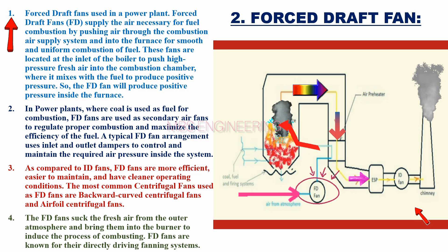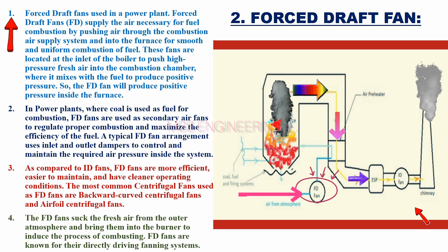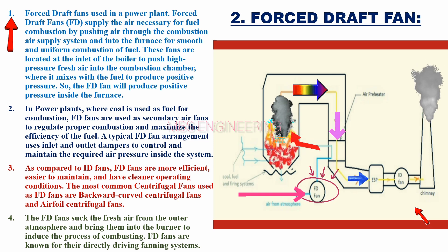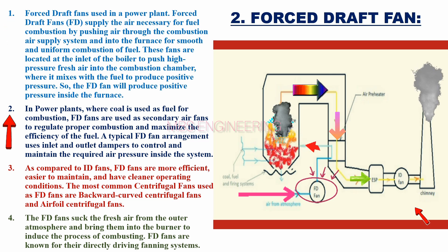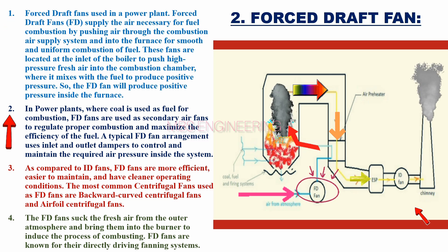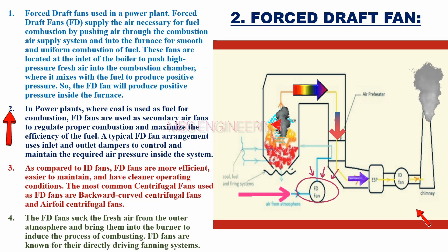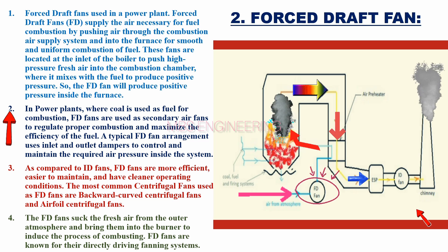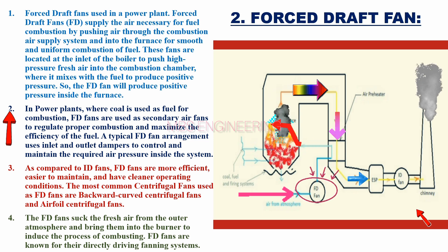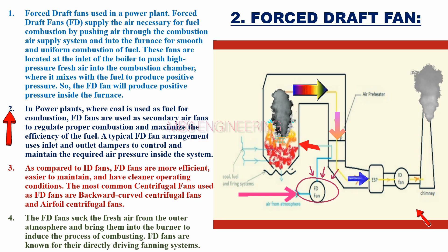Forced Draft Fans supply the air necessary for fuel combustion by pushing air through the combustion air supply system and into the furnace for smooth and uniform combustion of fuel. In power plants where coal is used as fuel for combustion, FD fans are used as secondary air fans to regulate proper combustion and maximize the efficiency of the fuel. A typical FD Fan arrangement uses inlet and outlet dampers to control and maintain the required air pressure inside the system.